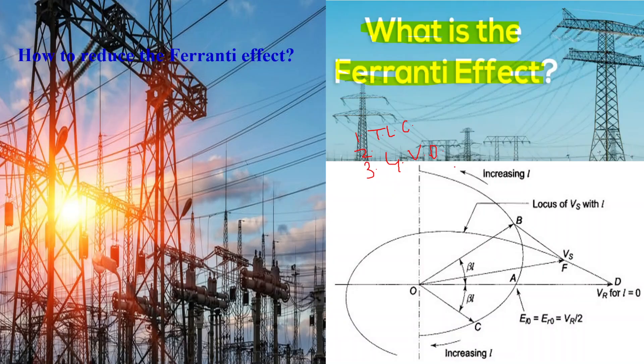Eighth, voltage rise. Due to the charging current and the reactive power flow, the voltage at the receiving end of the transmission line can be higher than the voltage at the sending end, especially under light load conditions when the line is lightly loaded or unloaded.